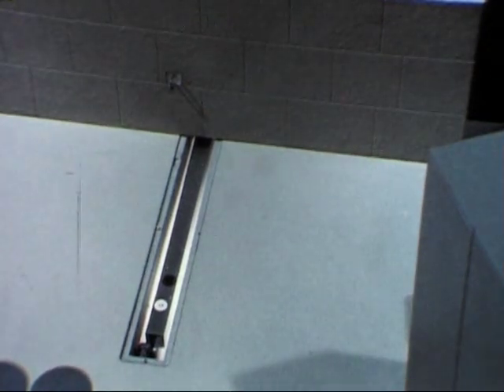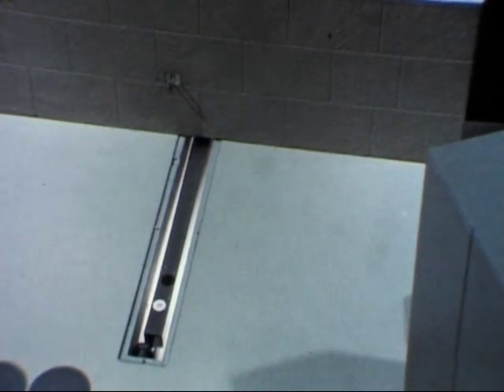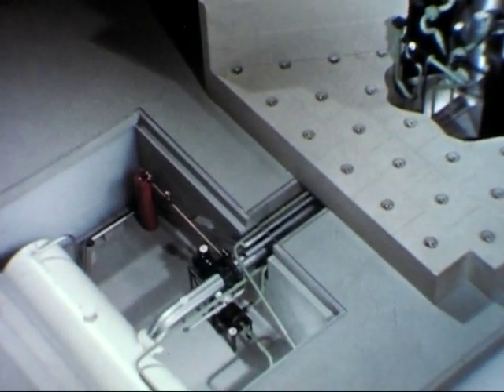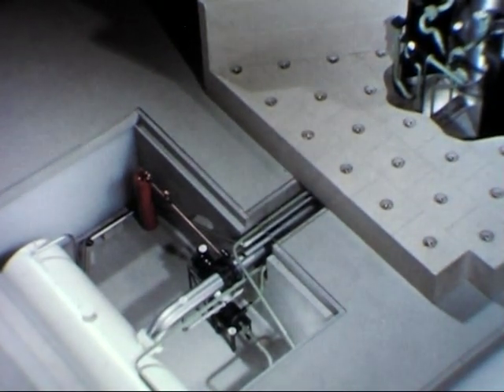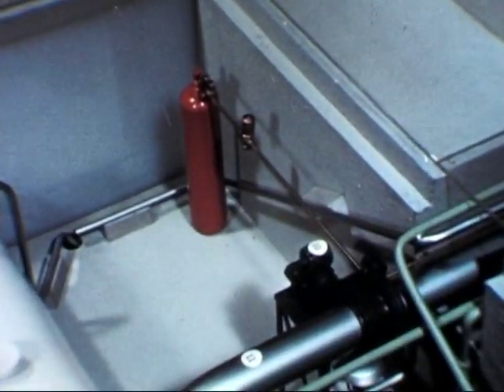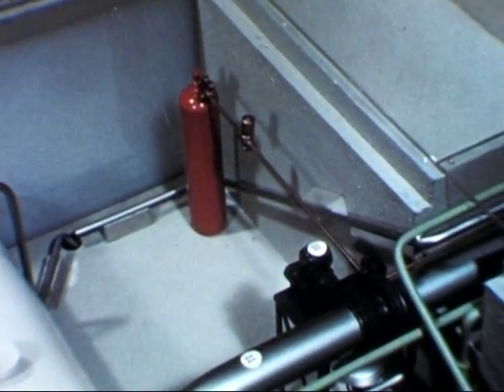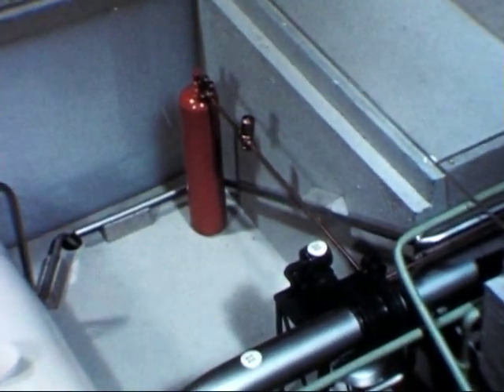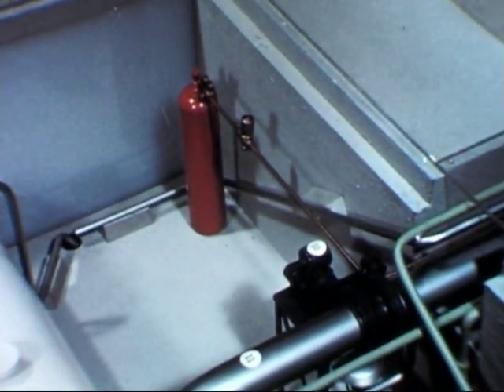A driving mechanism for running an antimony beryllium source under the reactor introduces neutrons to initiate startup procedures. Equipment to handle the natural water used as moderator and coolant is conventional, and an ion exchange system is used to purify makeup water. Nitrogen injection is one of the safety systems; gas bubbles can be used to replace water between the fuel plates, just as steam bubbles do in a boiling reactor, reducing the nuclear reaction rate and providing rapid shutdown.